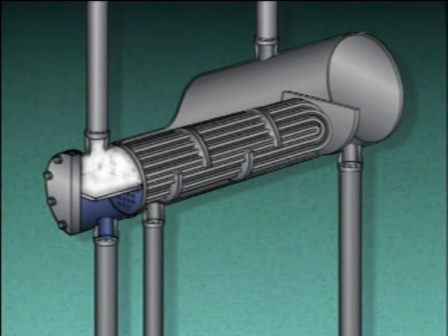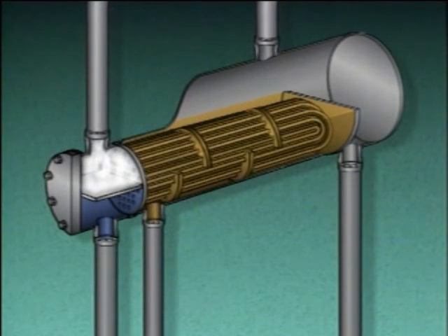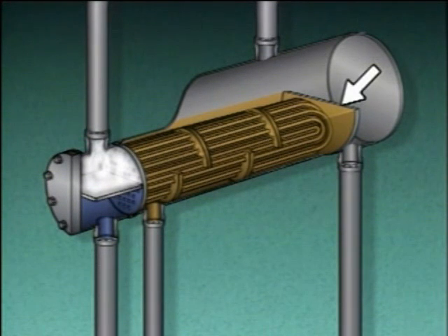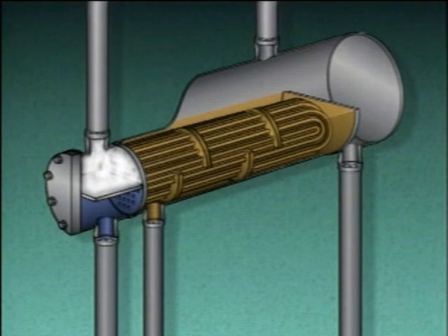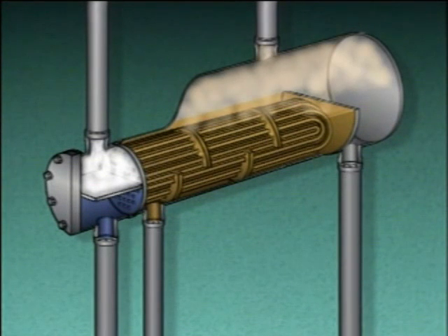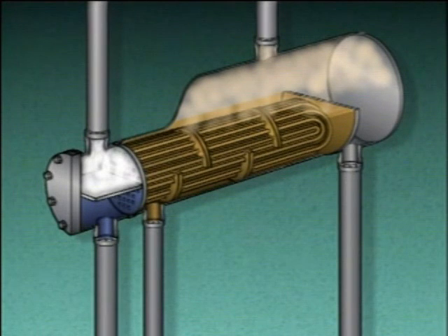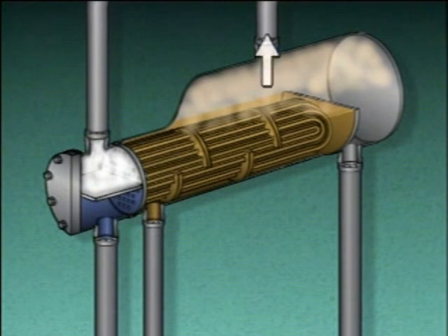The process liquid from the distillation column enters the reboiler here. The liquid flows around the baffles and tubes and receives heat from the steam. The overflow weir acts as a dam to ensure that the tubes in the reboiler always stay covered with the process liquid. As the process liquid is heated, some of the liquid boils off as a vapor. The vapor separates from the liquid and collects in the dome shaped space above the tubes in the shell, and then flows back to the distillation column.